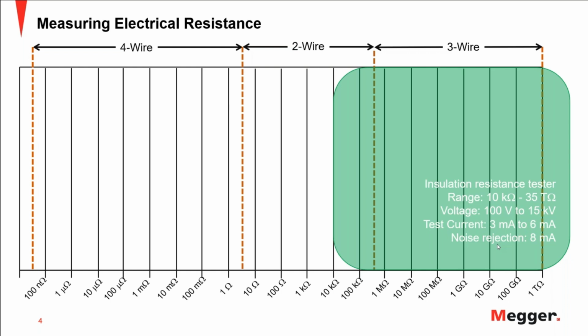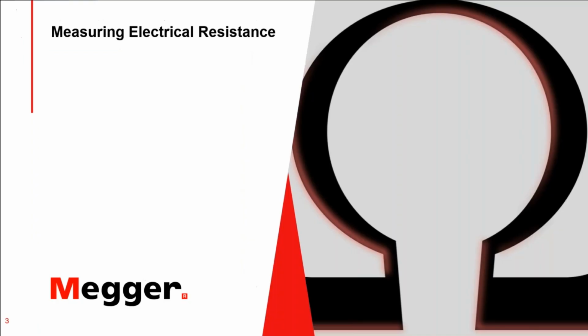Under these conditions of measuring such a low current, you're very likely going to have noise in some of the environment or some of the conditions that you test. So you want to have some noise rejection. So typically instruments can go up to 8 milliamps of noise rejection.